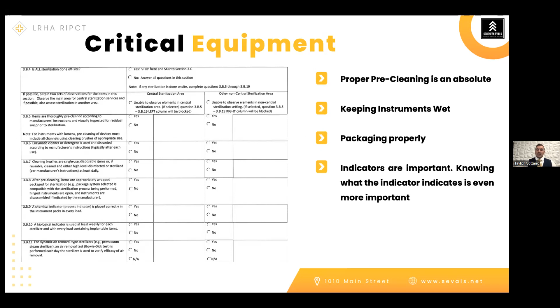And the last thing is indicators. Whether you've got a chemical indicator or a biological indicator, having those present if they're required, and then actually knowing what they mean. We've had instances where we work with facilities and they had the indicators in there, and whenever surveyors ask us, did this pass? They didn't know. They didn't know what a pass or a fail was. So making sure that your staff understand what the indicator means or how it reads if it passes or fails is another important part that you want to have in your program.